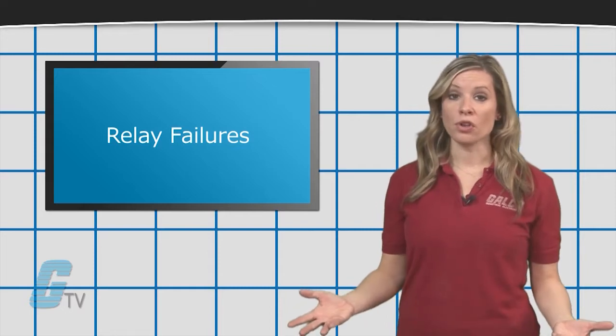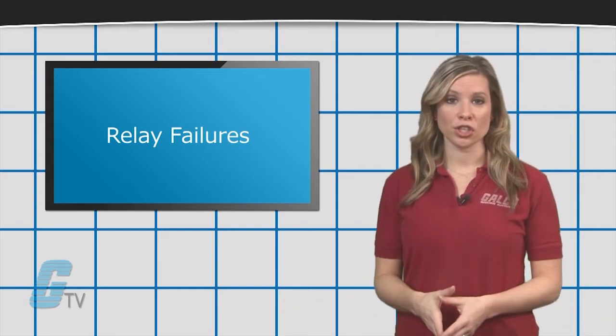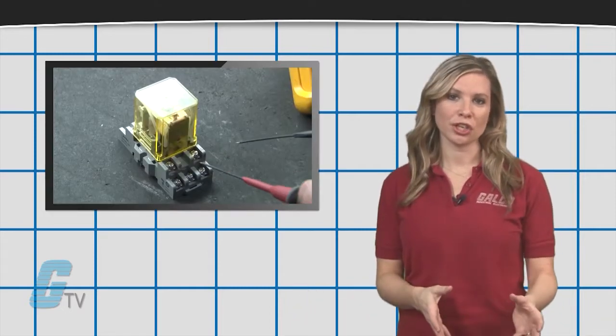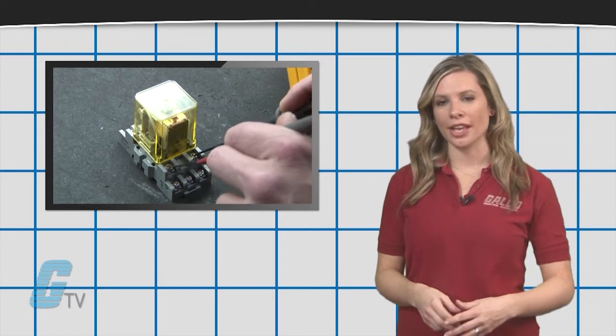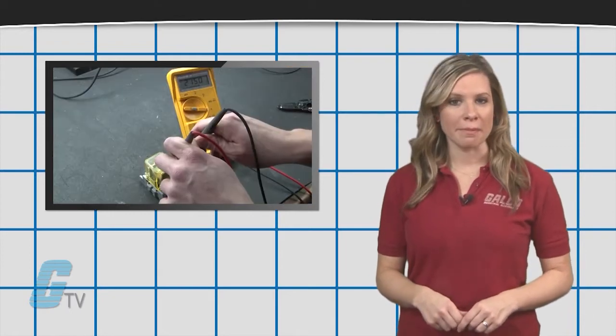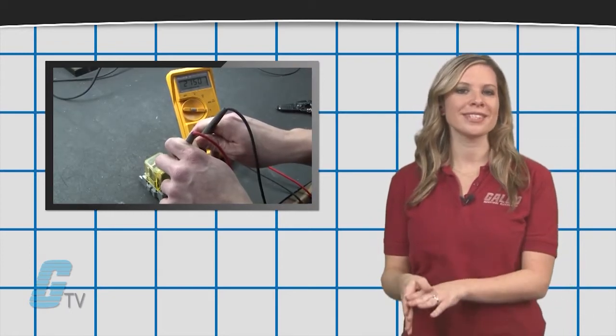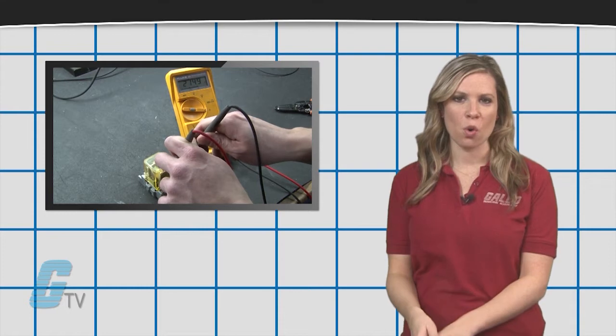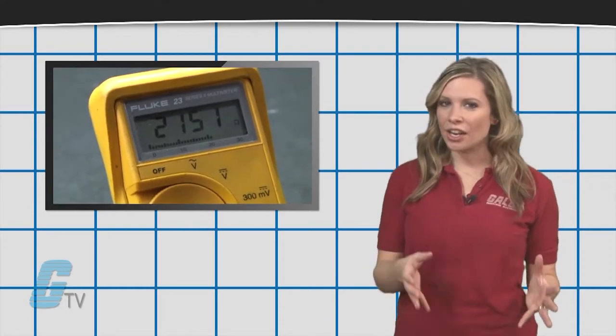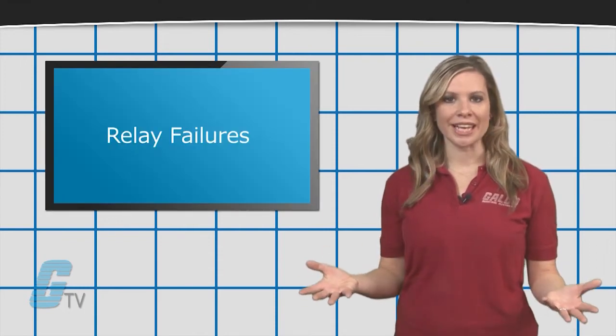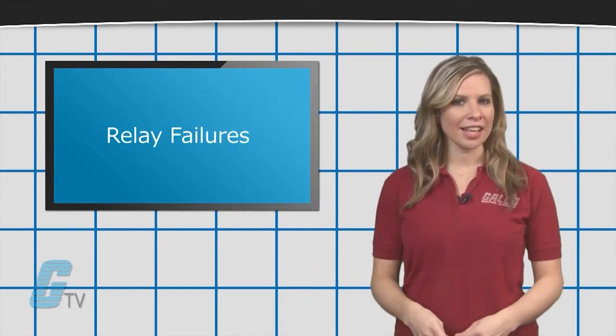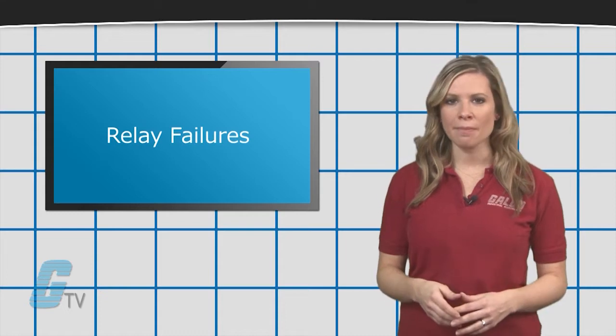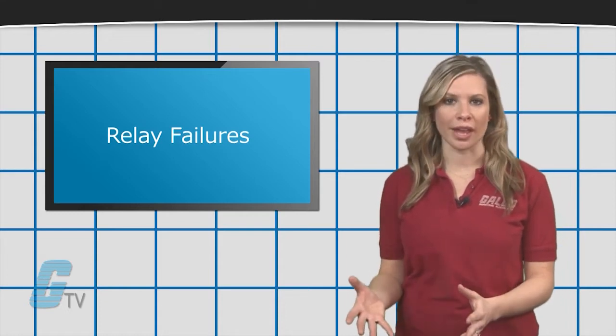The relay may not be broken and could still be functional. To determine if the coil is in working operation, a multimeter can be used to check the resistance of the coil. If there is some resistance and not an OL or infinite on the multimeter, then the coil is most likely in working condition and the issue may be with the wiring to the unit.